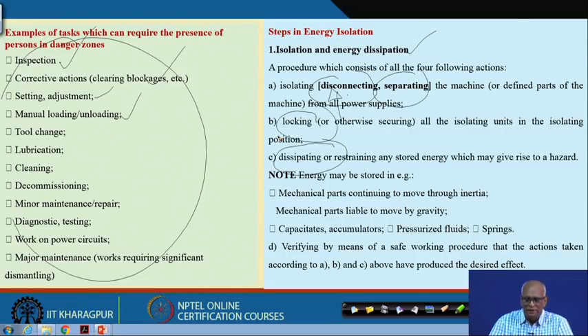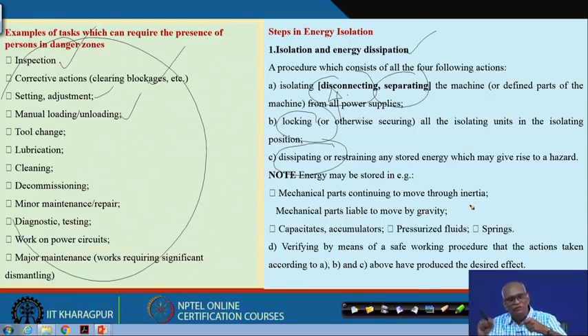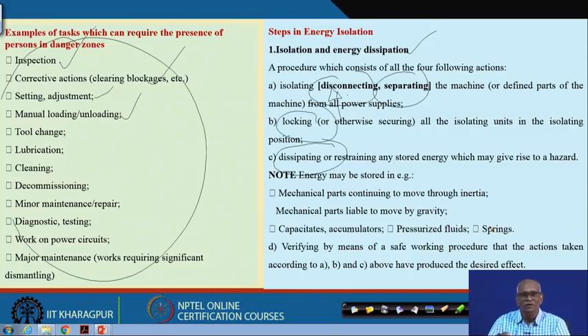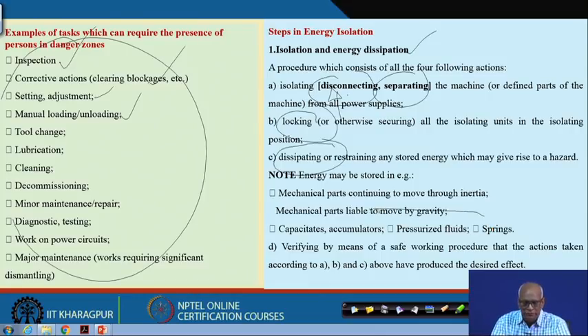Isolation is not complete unless you dissipate the stored energies. Energy storing means mechanical parts continue to move through inertia — flywheels, even if you put off the power, will keep rotating. In electrical circuits, capacitors store energy; in gas systems, accumulators; pressurized fluids and springs also store energy. All these things are to be dissipated and de-energized.